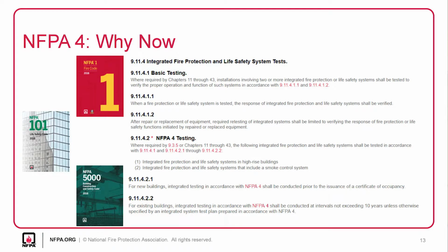The 2018 editions haven't really been adopted anywhere. And it could become something with a lot of fire alarm testing, because if you're testing a fire alarm, now you have to test the response of every system connected to it, which essentially becomes almost a full-blown integrated system test. To what degree the authority having jurisdiction is going to accept your testing is all up to them.